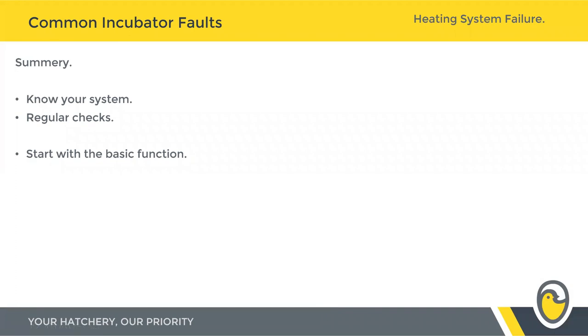Carry out regular checks on your machine. Those preset checklists are an absolute godsend for identifying early problems — they're also a great way of teaching newer maintenance staff or operators the basic functions of your machine, forcing them to go into those test screens and look around the incubator in a clean environment with no stress. When there is a problem, it's not a scary control system they suddenly have to learn and troubleshoot at the same time. As with all of the previous ones, start with the basic functions in test mode, force the outputs, see what activates, and work your way down the tree to get to the faulty component.